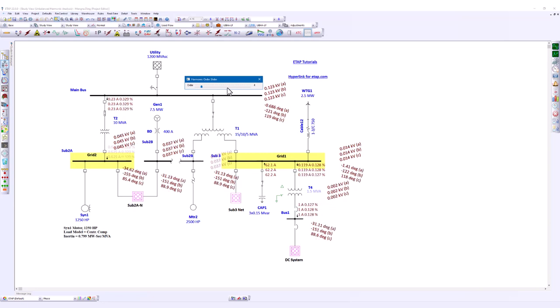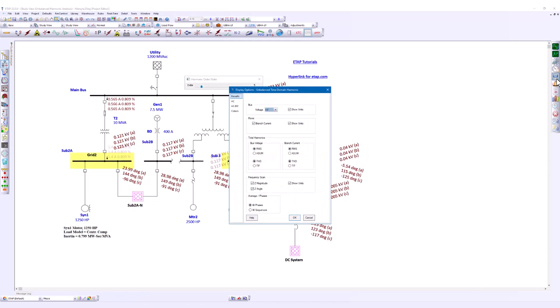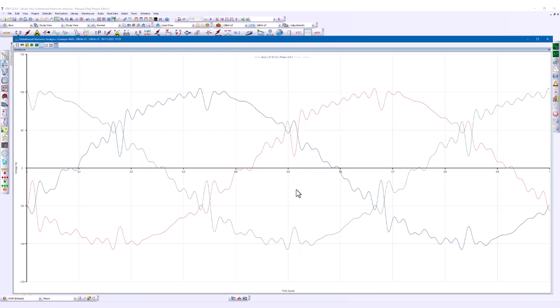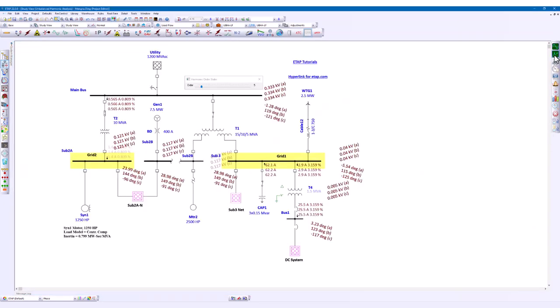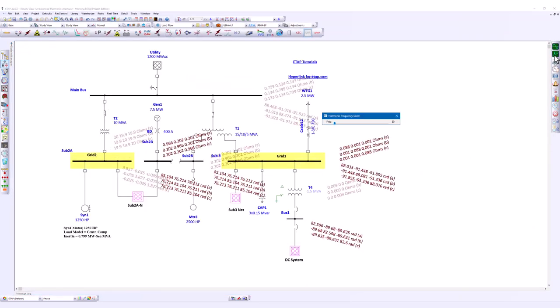the individual harmonic levels. If we take a look at the display options, there are options for displaying harmonic results per phase or per sequence. The plots can be done per phase as well. As you can see in this waveform, we have bus 1 plotted, with curves of phase A, phase B, and phase C. Similarly, you can run frequency scan on the unbalanced system as well.